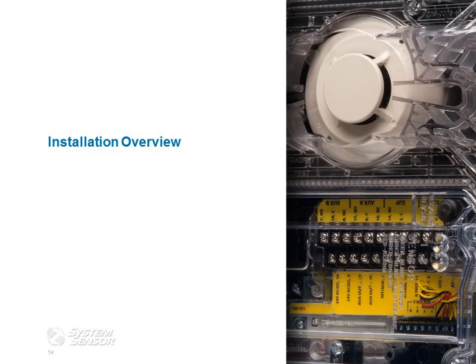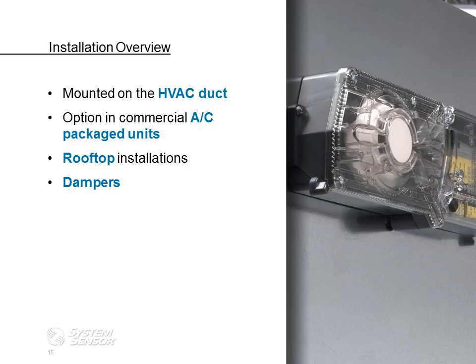Okay, thanks, Deb. All right, now we're going to begin the installation overview. And again, this is going to be high-level information, so if we need more detail, please feel free to ask questions or we'll cover follow-up. Where can we see installations of duct smoke detectors? Where are they installed? They can be mounted on HVAC ductwork inside the space. They are also available as an option in commercial AC packaged units. So most rooftop manufacturers offer duct detectors factory installed as an option in the rooftop installation. And then you'll also see them on dampers.